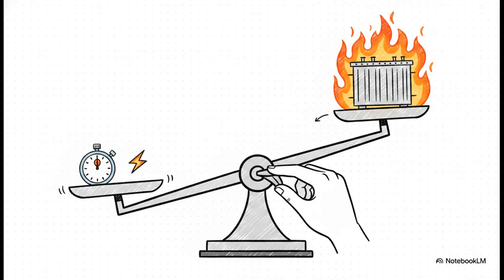So how long do we actually wait before pulling that emergency lever? Finding the Goldilocks zone here is absolutely crucial. A normal breaker might take 30 to 80 milliseconds to operate, while a typical failure timer is set between 100 and 200 milliseconds. If you set it too close to that 80 millisecond mark, you risk massive nuisance trips just because a perfectly healthy breaker was a tiny bit slow. But set it too long, you exponentially increase the severe physical damage to your transformers and conductors during a genuine fault. Literally, every extra millisecond a fault persists scales up the physical damage.